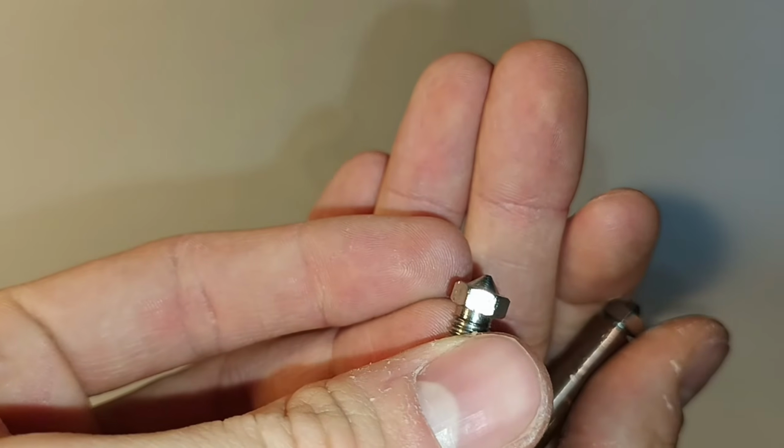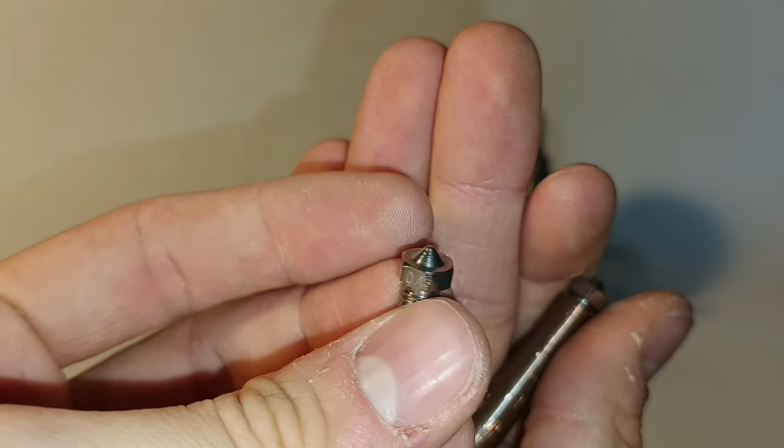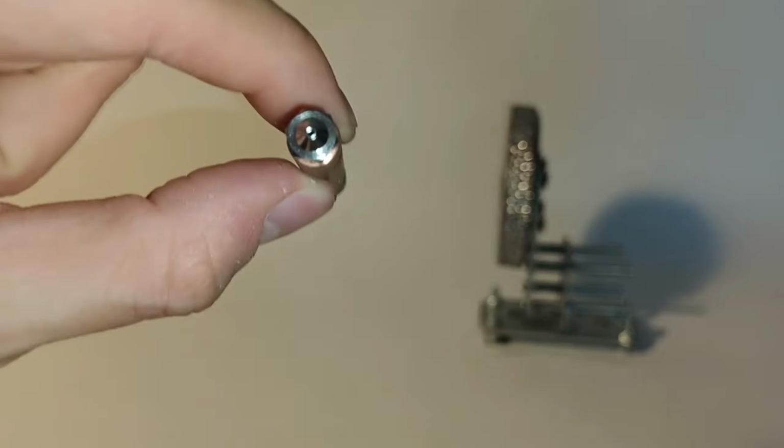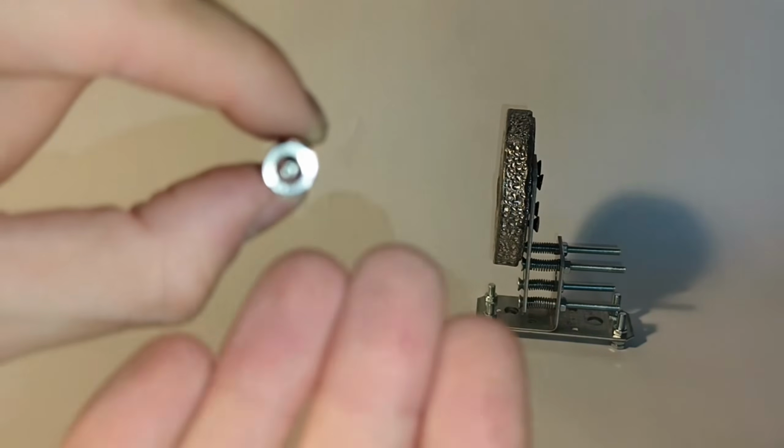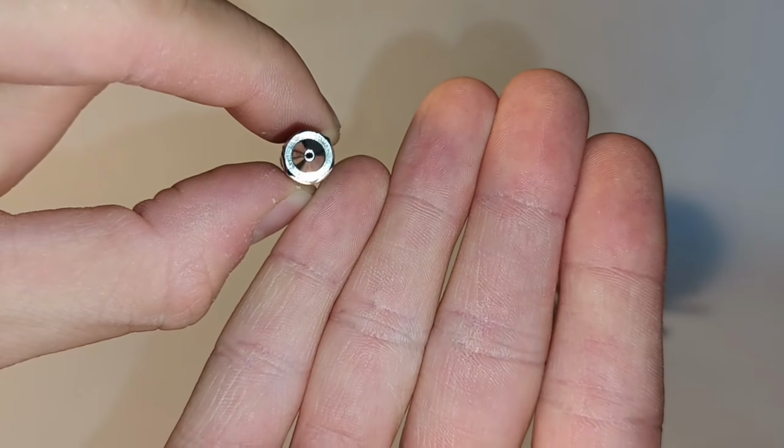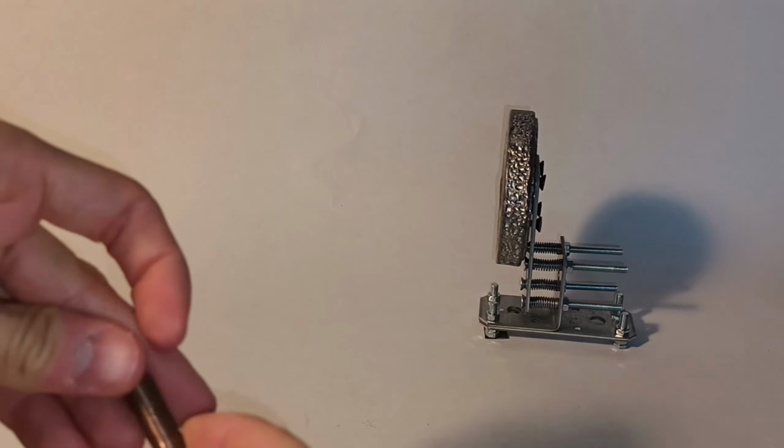As you can see, a 0.4 mm hole, the other one is a 1 mm hole, and you can see through it. These 2 in series create the collimator system.